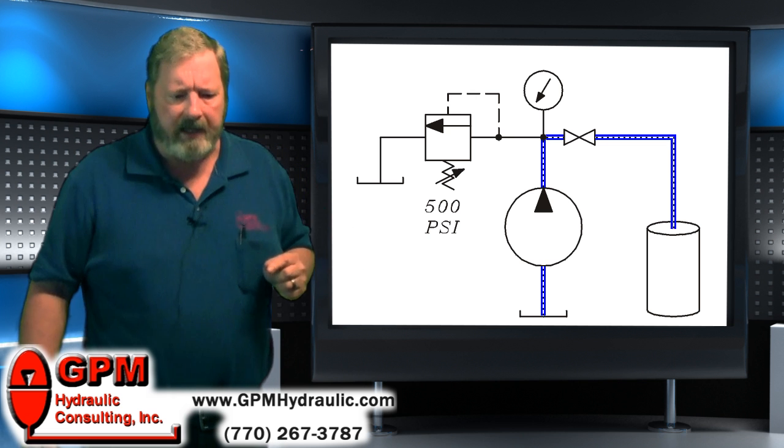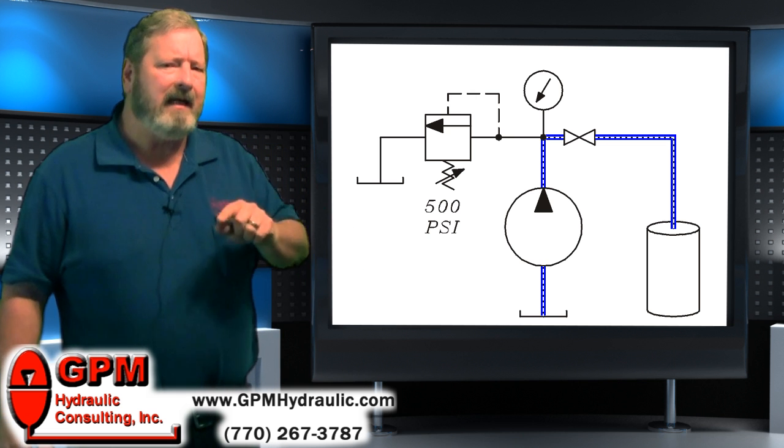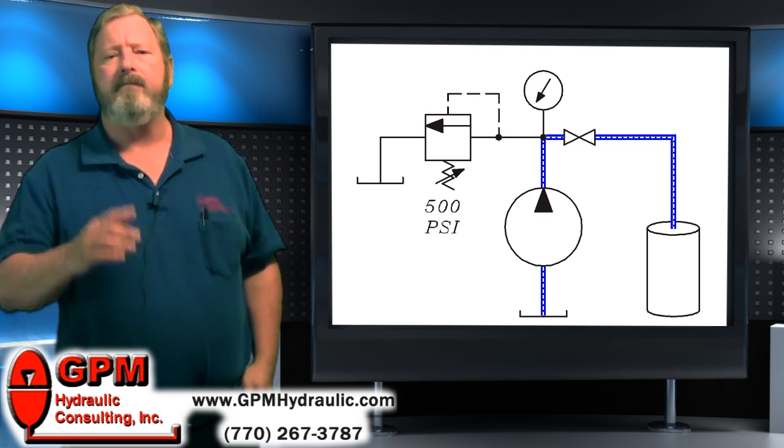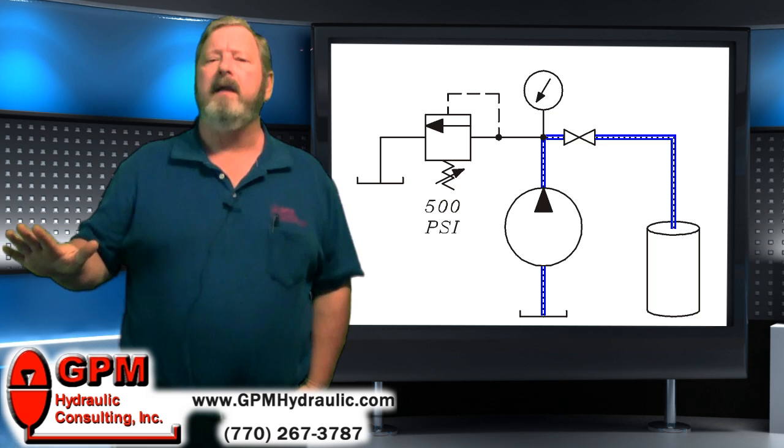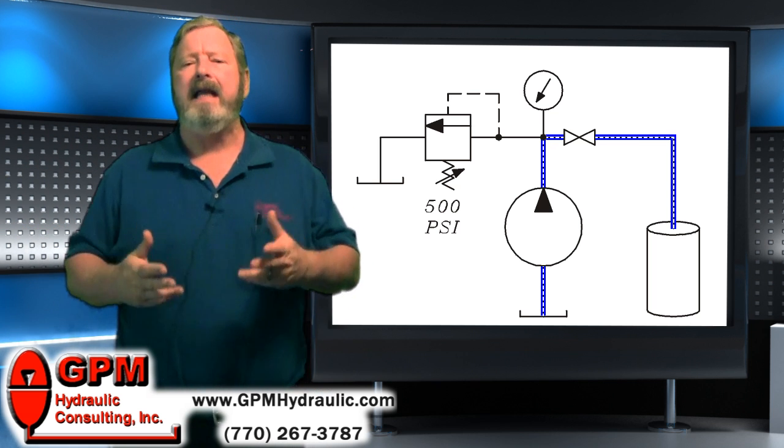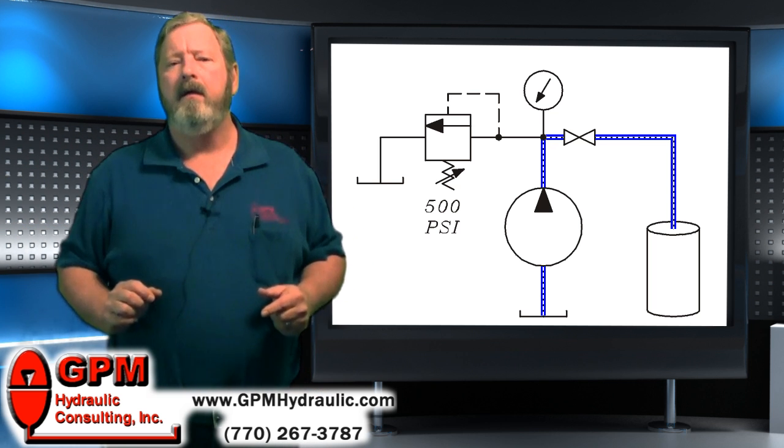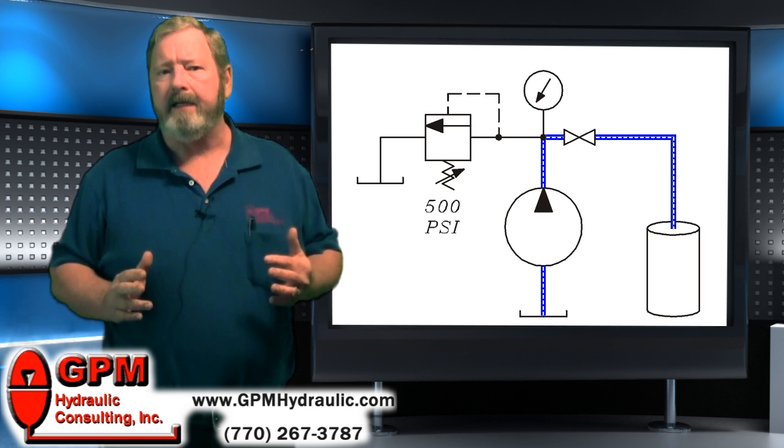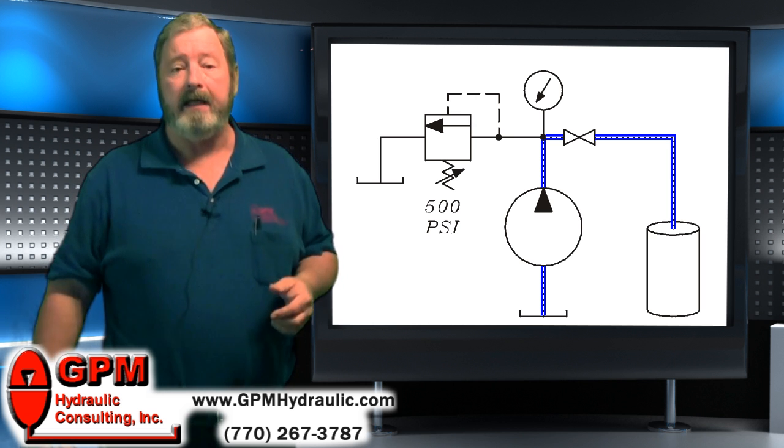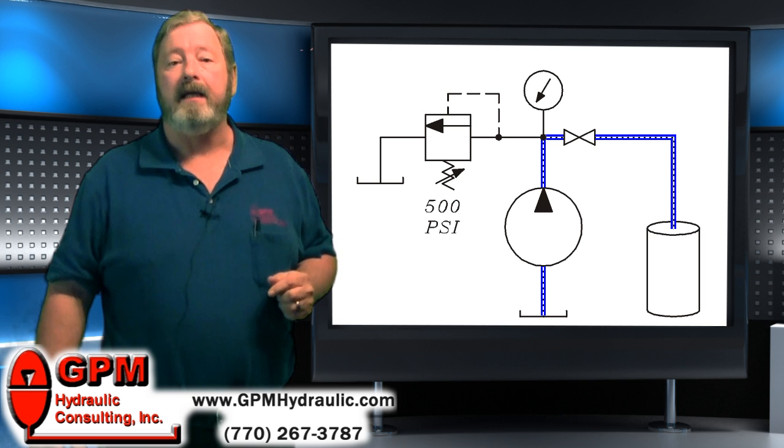But let me ask you a question. How many times have you seen a pump changed for no other reason than because the gauge read zero or lower than someone thought it should be? Personally, I've seen it hundreds of times and it's typically a mistake.